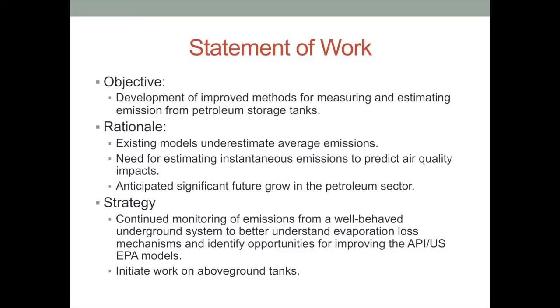One of the weaknesses in the existing API algorithms is that, if you read the documentation, they're recommended for use in developing emission inventories for assessing annual average emissions, but not for designing vapor control systems and not for determining instantaneous emission rates. If you're doing an air quality assessment and trying to predict impacts on receptors, you need to understand what the peak emissions will be and what the variability in those emissions would be. That was part of what we were trying to address as well.